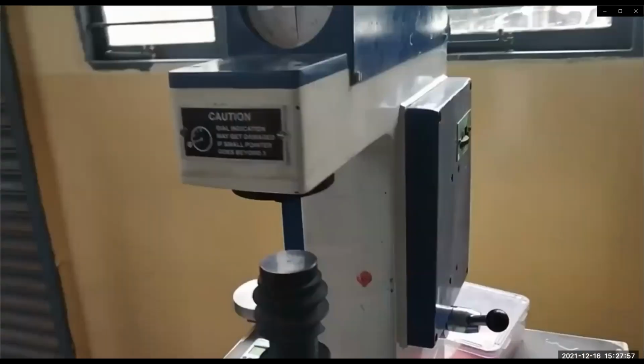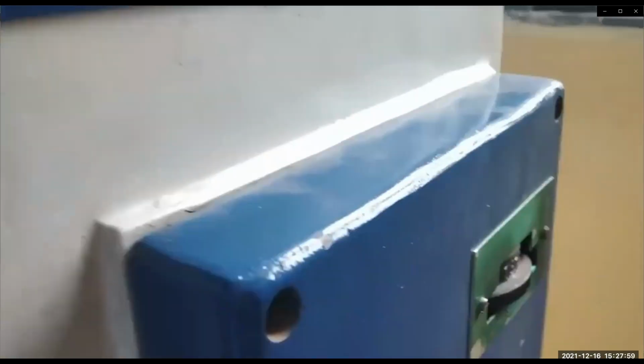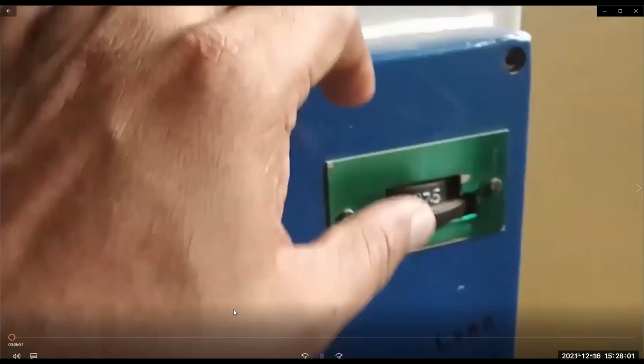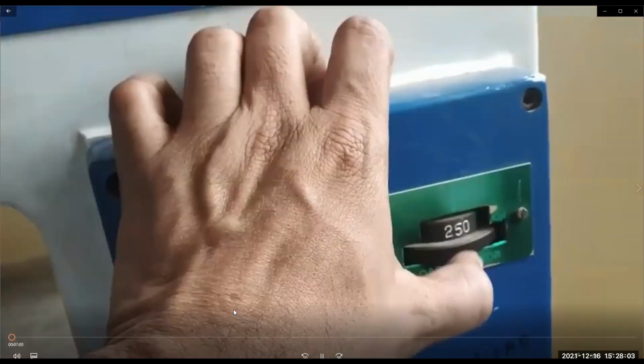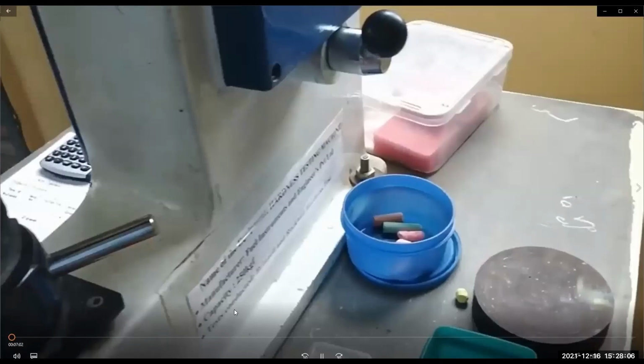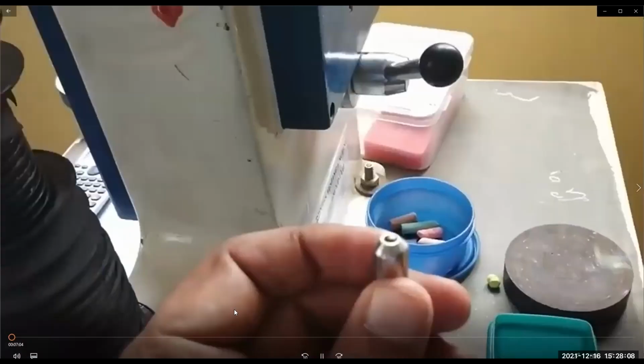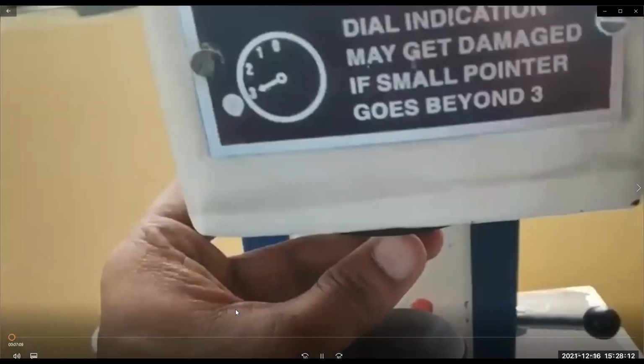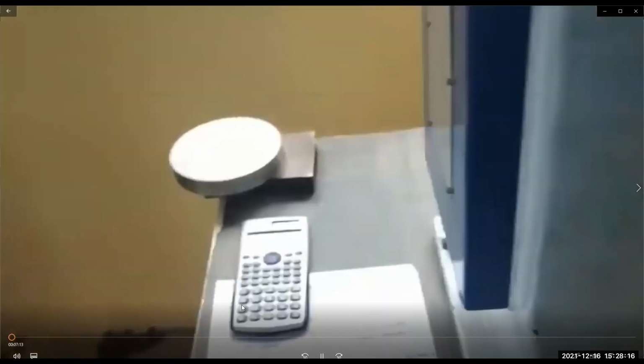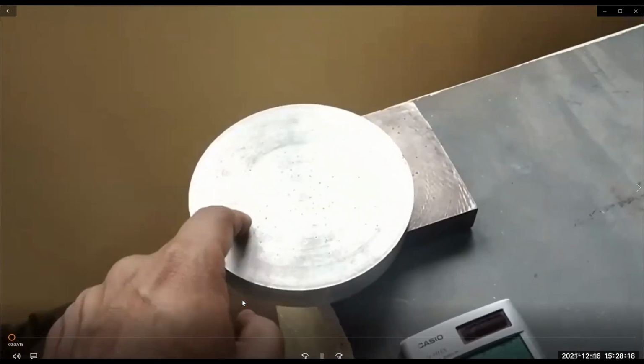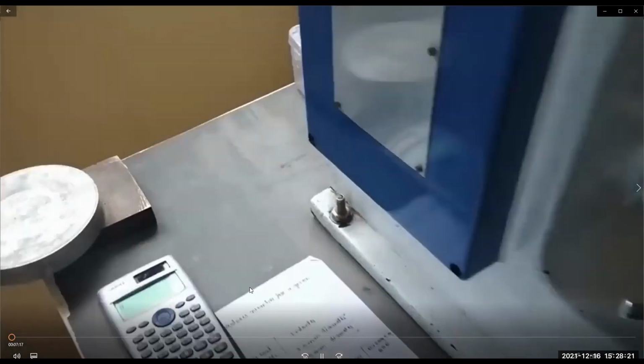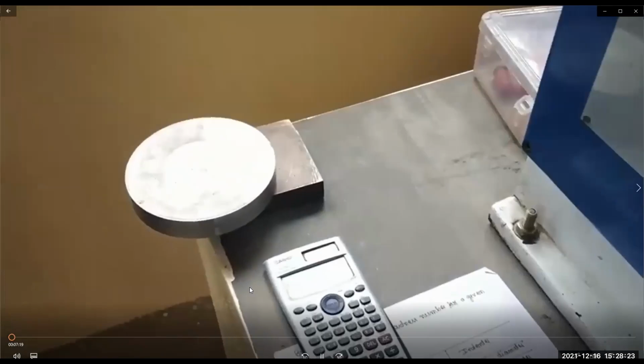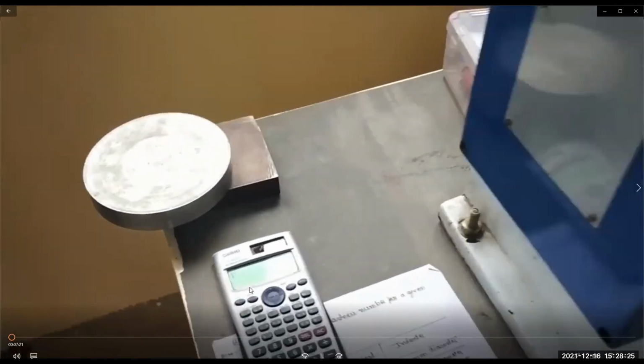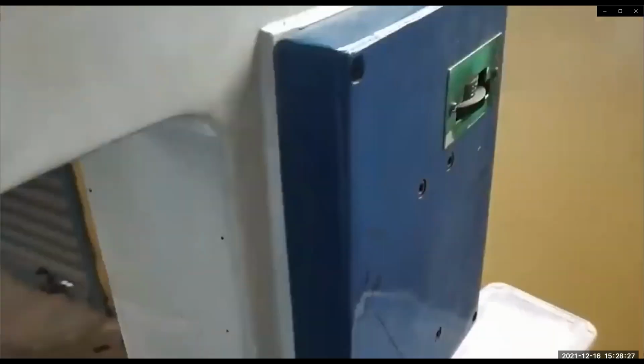In case of non-ferrous material, please change the values. Load 250 kg and the indenter will be 5 mm, and it has to be fixed here, and you have to repeat the procedure. The same procedure you have to repeat, taking the readings over the specimens. These are the specimens, aluminum and brass, and you have to check them under the microscope. The same procedure you have to repeat. You have to wait for 1 minute here.